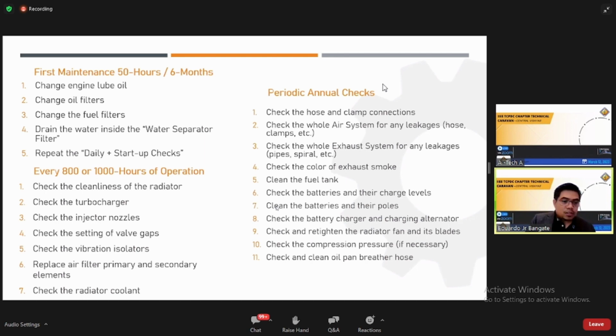So check, I will give you an example of that later, about the problem with the valves, the wrong valve gap setting. So check the vibration isolators. Replace air filter primary and secondary elements. Check the radiator coolant. Now, periodic annual checks. Check hose and clamps. Check the whole air system for any leakage.